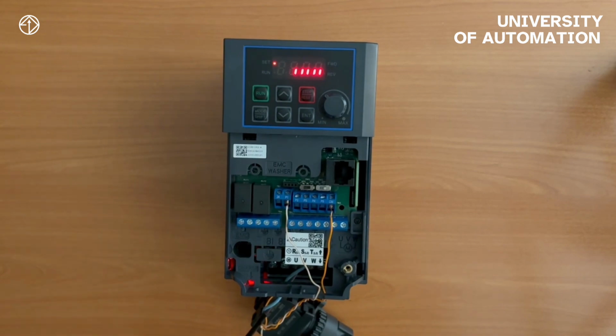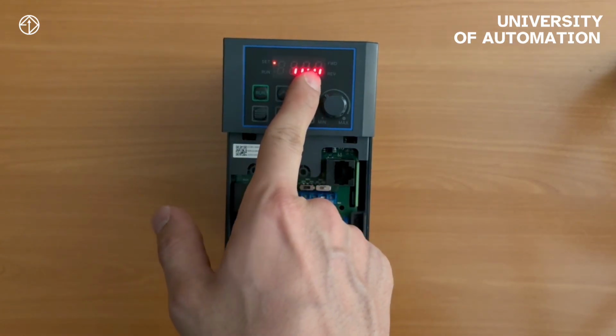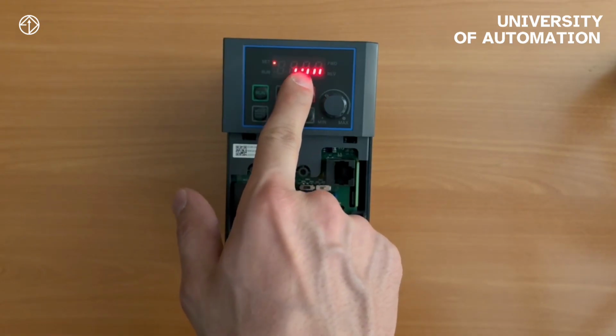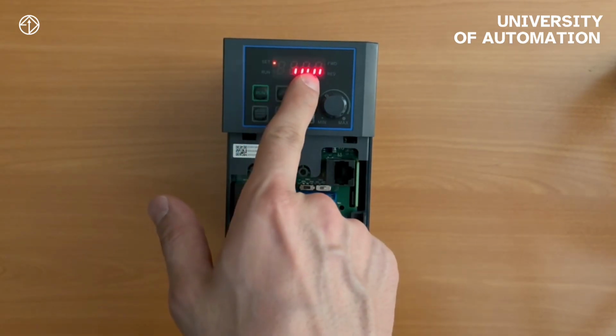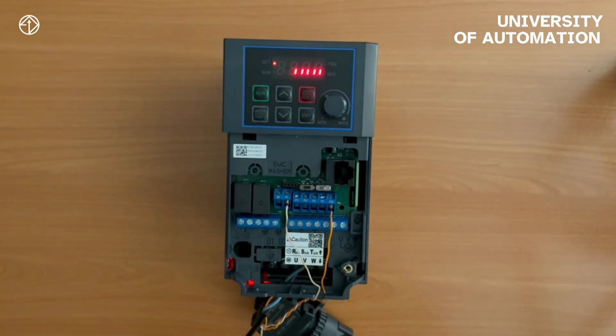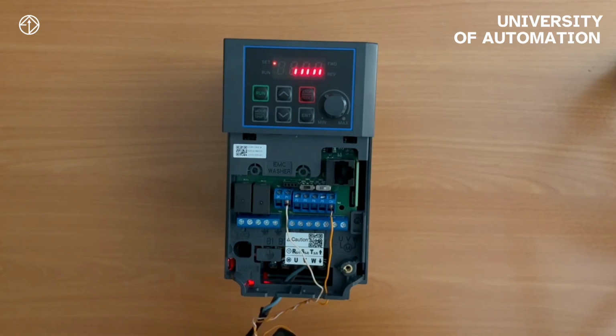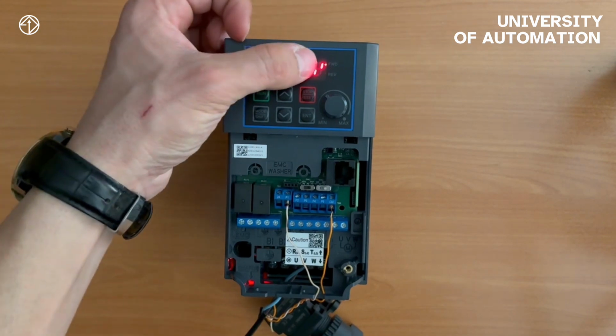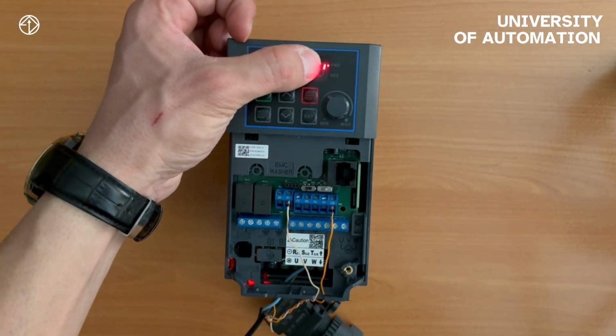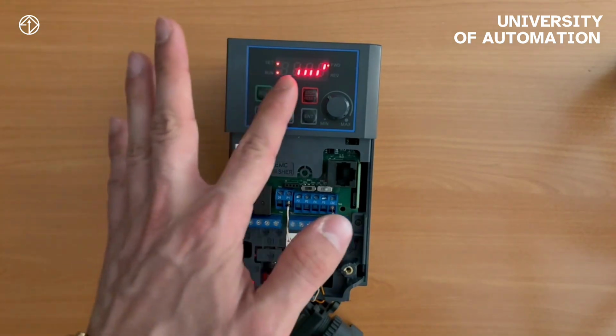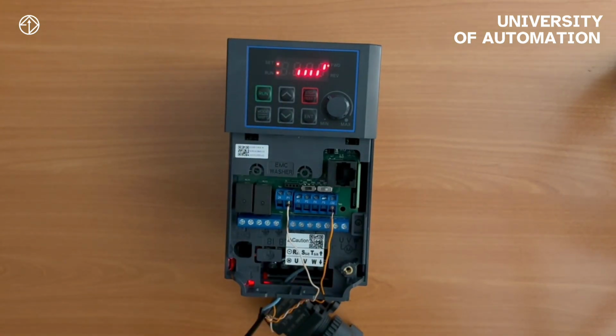We can observe whether our digital input is currently active or inactive. So, as we said, if this bit, which from the right side is again P1, P2, P3, P4, and P5, is high, meaning it's active, it shows that our digital input is currently active. If it's low, it shows that our digital input is inactive. Now I'm going to activate the digital input P1. Since we set a delay for it, as soon as my digital input is activated, now it shows that my digital input P1 is in the on state. So in parameter 90, you can also view the status of your digital inputs.